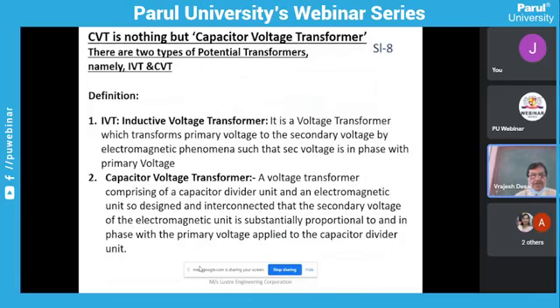IVT. What is IVT? It is an inductive voltage transformer. We transfer primary voltage to the secondary voltage by electromagnetic phenomena, such that the secondary voltage is in phase with the primary voltage. Capacitor voltage transformer, same thing, voltage is transferred, but it is transferred through a capacitor divider, and it has a small electromagnetic unit, so designed and interconnected that the secondary voltage of the electromagnetic unit is substantially proportional to and in phase with the primary voltage.